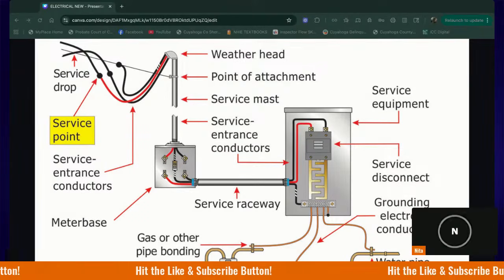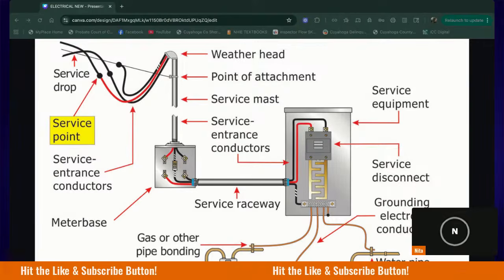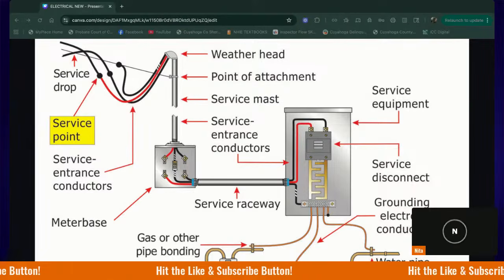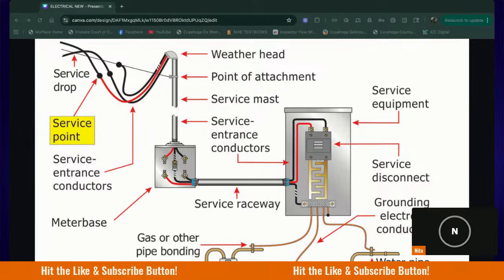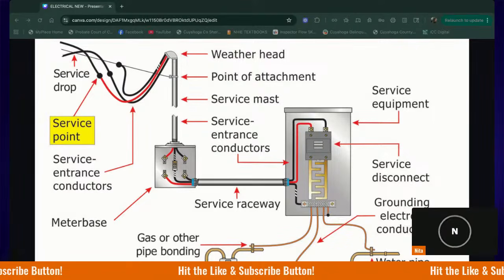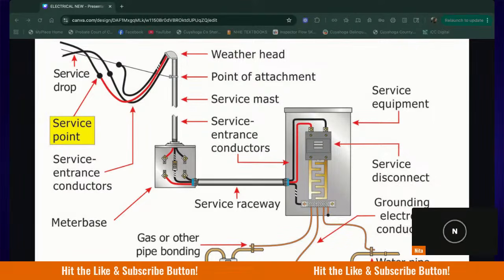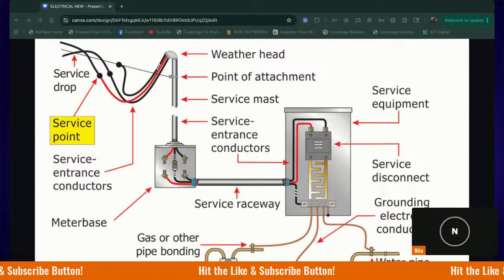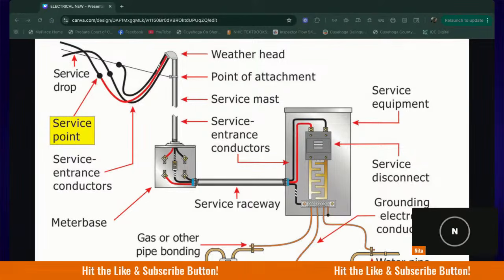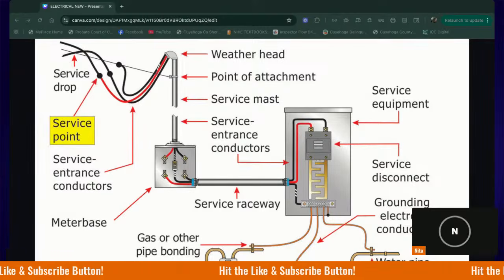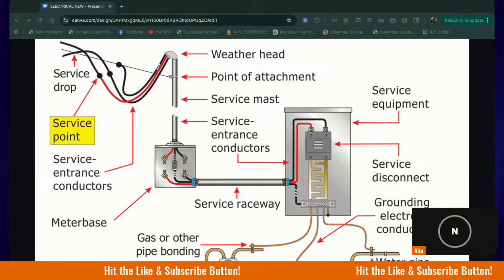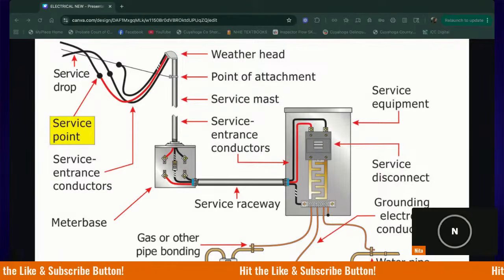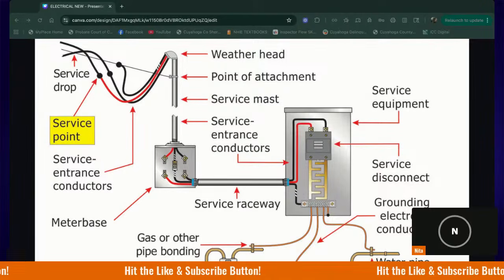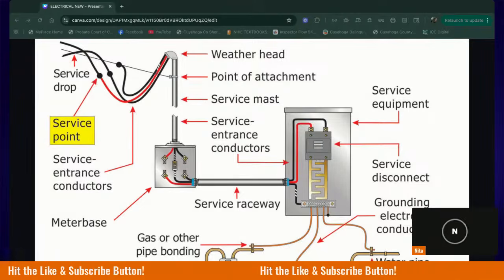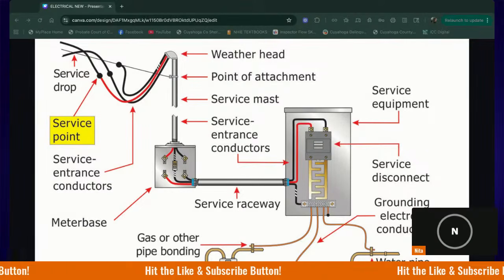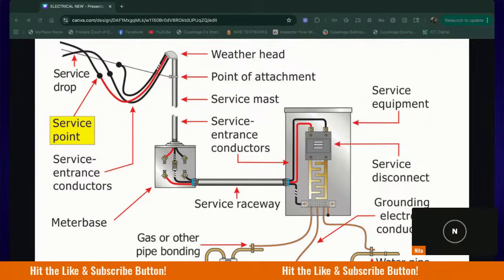You told me that what happens next in step 3 is the service point. I want to know if I visually had to identify the service point, what would I be looking for? You would see 3... I don't know the name of them. The only way I can describe them is like 3 knobs on those service drops. On each cable, you'll see like 3 knobs. Does anybody disagree? Because that's where it separates.